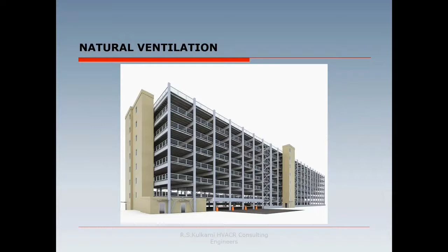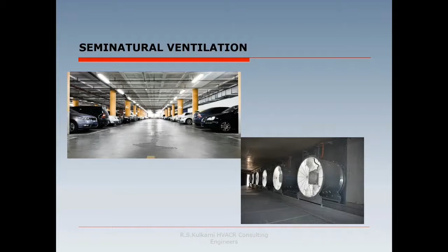Then semi-natural ventilation. This is where one criterion is met, like we have openings on one side of the wall and the other side is closed, or vice versa. Then we can follow the push method, where we push the air into the basement and the foul air leaks into the ambient through the ramps or other side openings, or else we can use the pull method. In this case, we exhaust the air to the ambient and suck the air from the other side without any ducting.